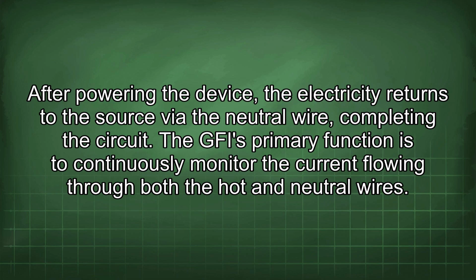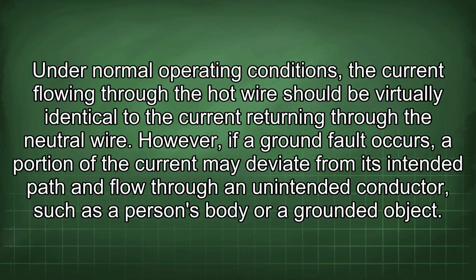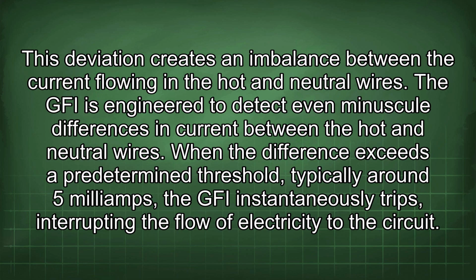The GFI's primary function is to continuously monitor the current flowing through both the hot and neutral wires. Under normal operating conditions, the current flowing through the hot wire should be virtually identical to the current returning through the neutral wire. However, if a ground fault occurs, a portion of the current may deviate from its intended path and flow through an unintended conductor, such as a person's body or a grounded object. This deviation creates an imbalance between the current flowing in the hot and neutral wires.